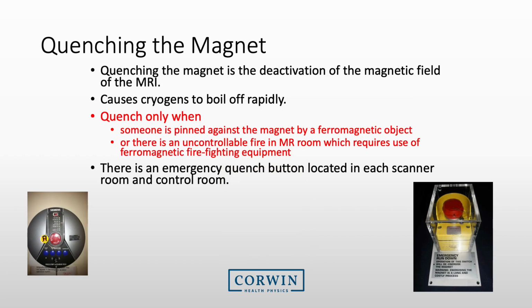Every technologist needs to know about the concept of quenching the magnet. The magnet maintains its magnetic field through the use of cryogenics, or very cold fluids. A quench occurs when you deactivate the magnetic field. This causes the cryogens to boil off rapidly. You should quench only under certain conditions, such as when someone is pinned against the magnet by a ferromagnetic object, or there is an uncontrollable fire in the room which would require firefighters to enter.